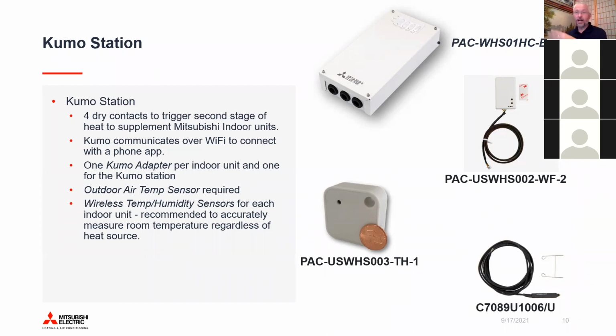So that same principle applies whether you're talking about this wireless Bluetooth remote or the placement of any other thermostat to do this measurement for 2 stages. It's really, really important to make sure that whatever is going to be measuring the temperature for a room to control temperature in that room has to be appropriately placed for either distribution system.